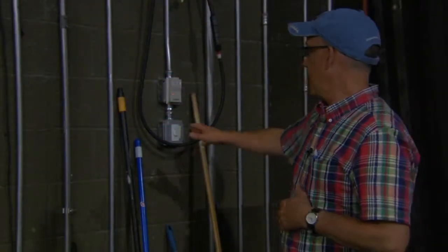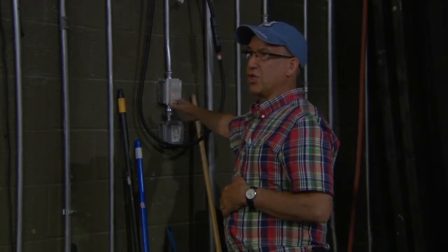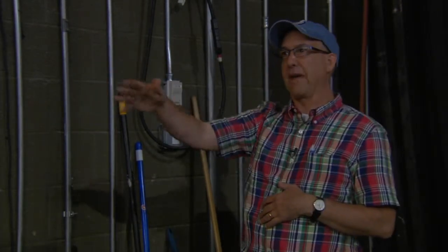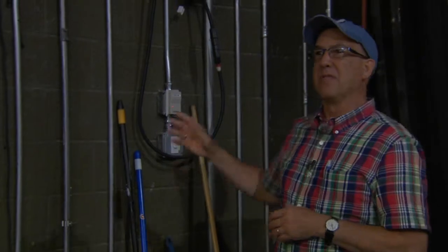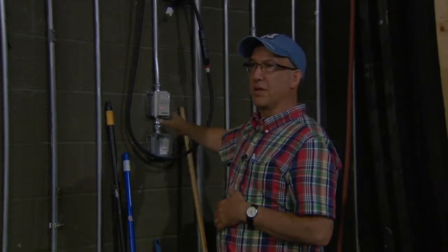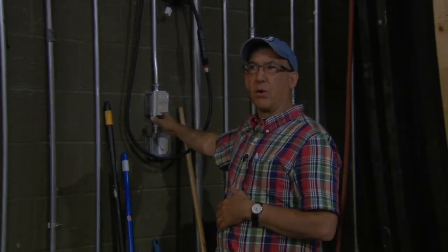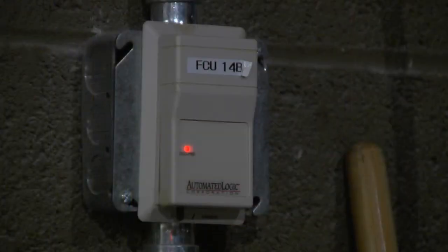So what we see right here is you've got a thermostat. There's one just like this over on the opposite side for fan coil 14A. If you look closely, there's a red light on. I've been told that means it's in an occupied mode. So it's hopefully on a schedule, probably the same schedule that we've seen for most of the other HVAC systems, maybe 6 to 11. Could it be tightened up?